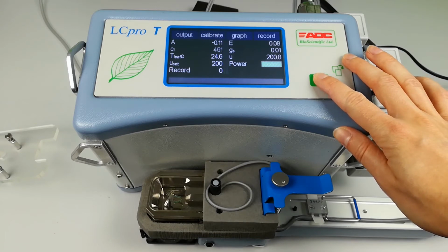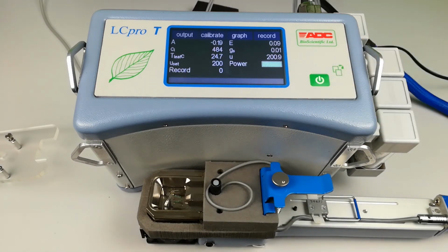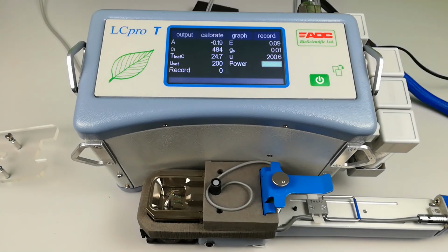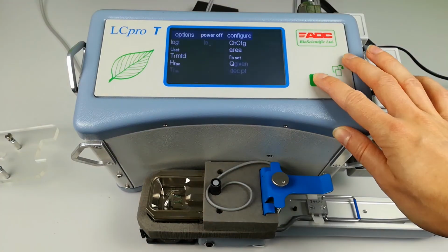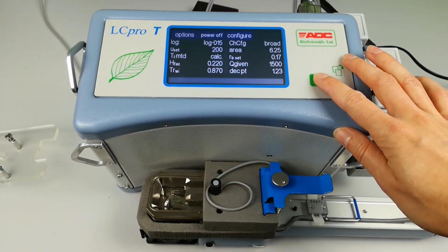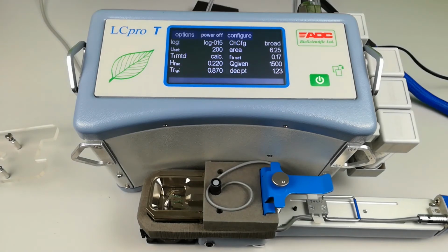This includes all calculated parameters, including photosynthesis rate, transpiration rate, stomatal conductance and substomatal CO2. Leaf temperature, set flow and actual flow rate are also displayed. A power bar indicates the level of battery charge. A count within the selected record file is also displayed. To reach main menu 3, swipe or press the Power Page button again.